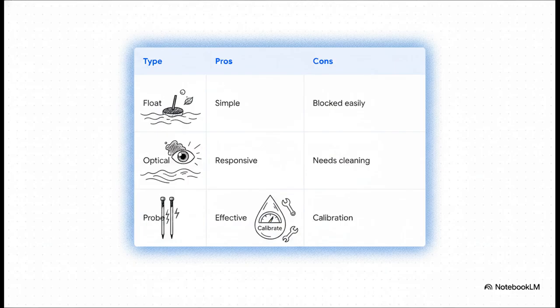Now, what's really interesting about this slide is how easily you can map out the trade-offs here. Float switches, for instance, are super durable and simple, but because they're mechanical moving parts, they can get stuck on stray bubbles or floating debris. Optical sensors are incredibly responsive using light, but if those little optics get dirty or if your tank has heavy water turbulence, you're going to get false readings. And finally, conductivity probes. They use electrical properties to detect water levels, which is highly effective, but they demand really careful calibration and consistent maintenance to stay accurate over time.